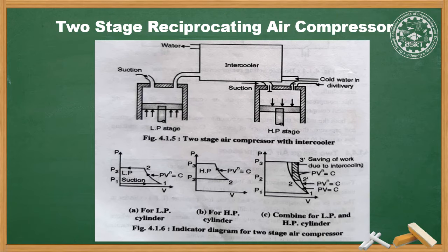The power required in a multi-stage compressor is less as compared to a single stage for the same amount of output, or for the same amount of discharge to be delivered. The intercooler is used where more power or more compressed air is required. Two-stage reciprocating air compressors are also used where the required delivery of air is high or the required air pressure is high.